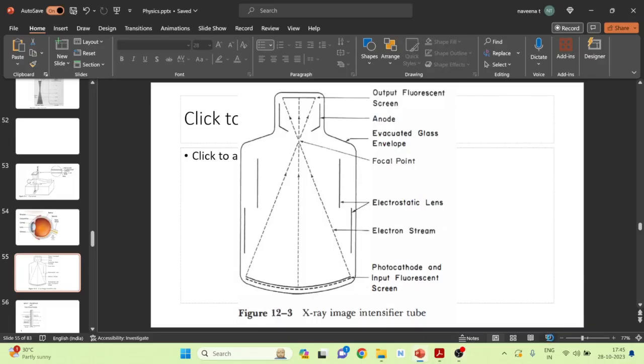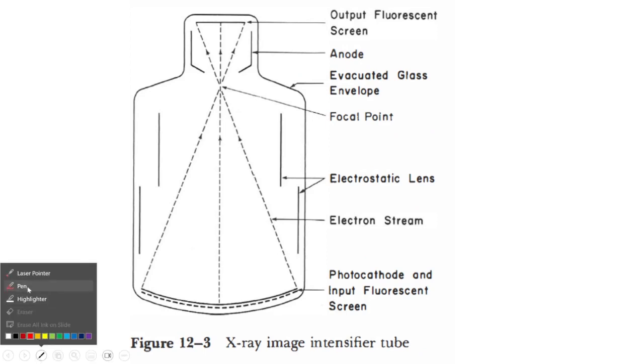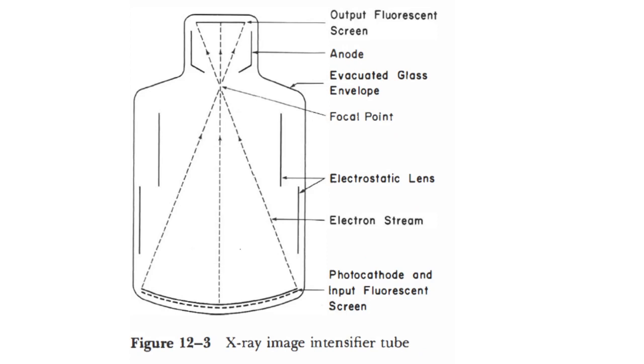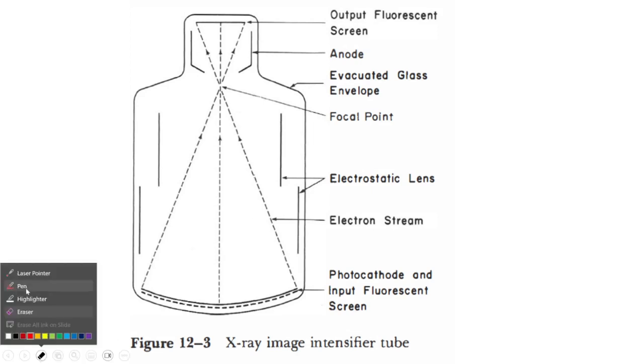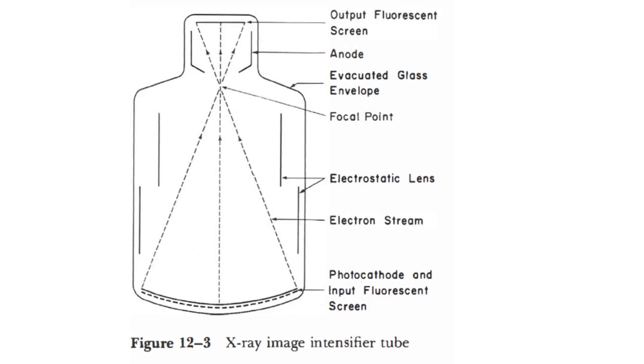Let us learn some important points about the image intensifier tube. This is a picture of an image intensifier tube. It is made up of an evacuated glass envelope. There are four important parts: the input phosphor and photocathode, electrostatic focusing lenses, an accelerating anode, and an output phosphor. When the X-ray beam passes through the patient, it enters the image intensifier tube.